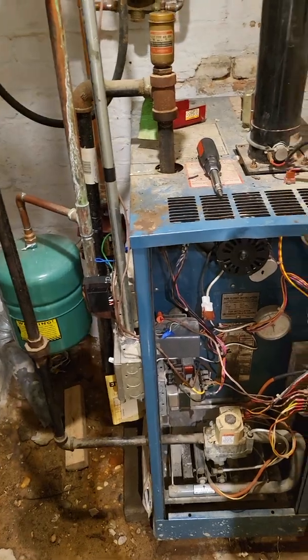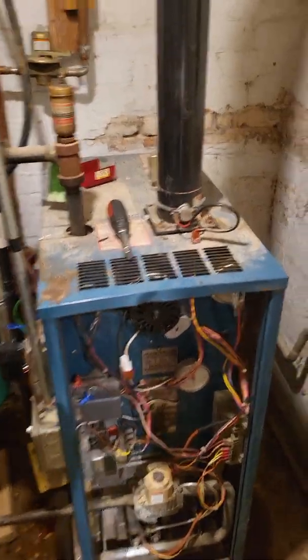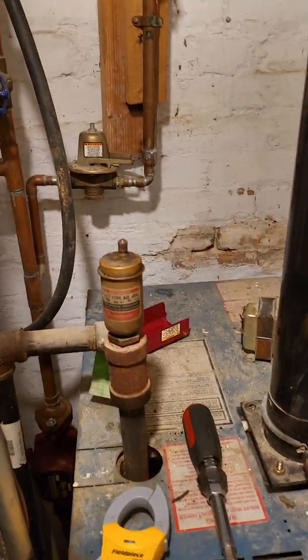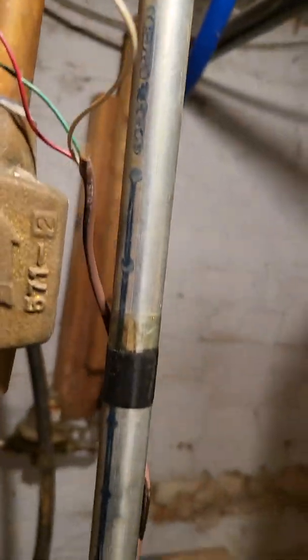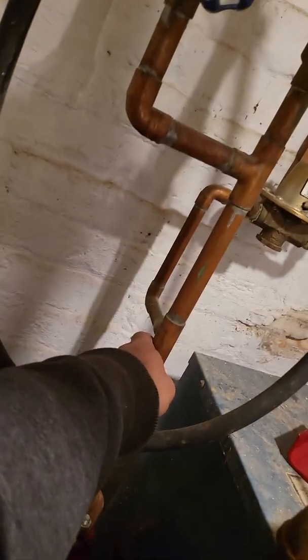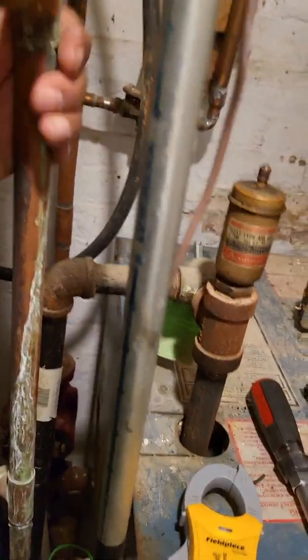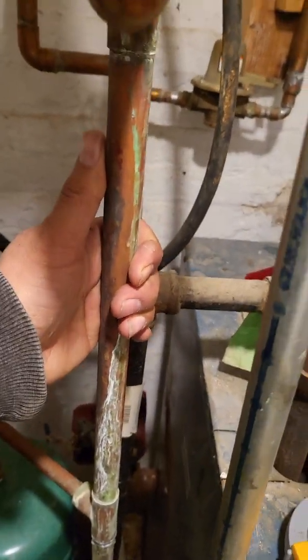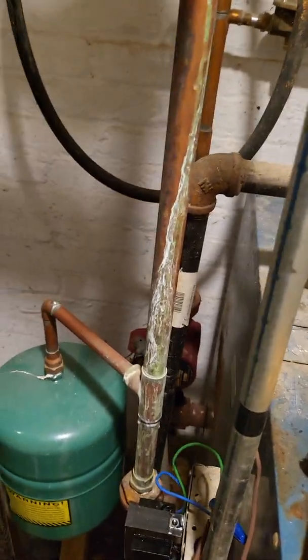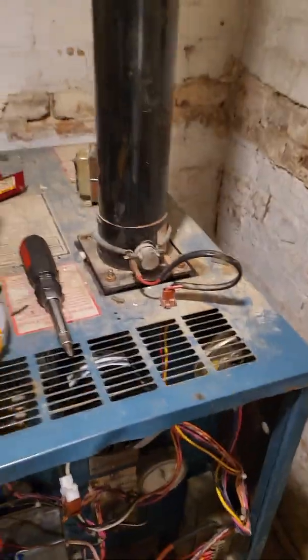As you hear now, the boiler stopped without satisfying the zones, and here is still cold, here is still cold, here is hot, here is hot. The return is hot close to the pump, and the supply is hot just close to the boiler, which means the circulator is not running.